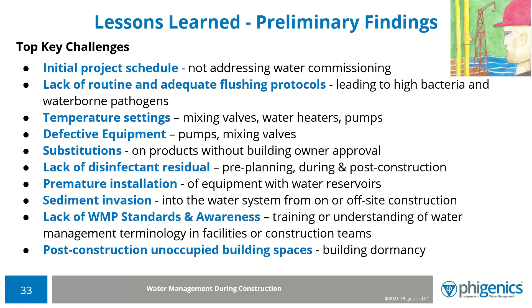An amazing number of building owners build a building that they do not occupy immediately, or they don't occupy it fully for quite some period of time. If that building is going to have large occupancy, you need to be aware of that so you can have an effective program coming out of commissioning to deal with the dormant parts of the building. Maybe some areas should be drained and not have their piping activated, et cetera.